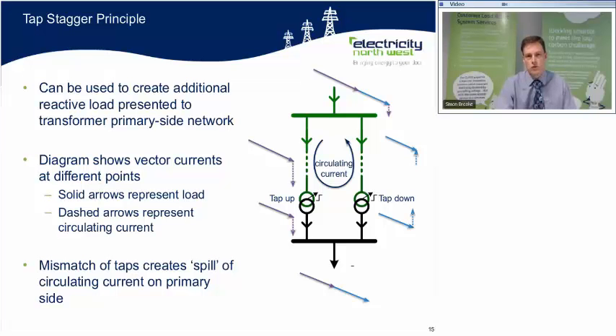As we move up to the primary side of the transformer, we will see the same shape, the same relationship of currents, but here the magnitudes vary, representing the fact that we are on different tap positions for each transformer. And then finally, as we get to the top, the vectors are superimposed again, with the solid lines representing the total load of the substation as seen on the higher voltage network. But now we see effectively a spill of circulating current, represented by the dashed line, as seen by the higher voltage network. And because circulating current is effectively a reactive current, what we have effectively created is an additional reactive load as seen by the higher voltage network.